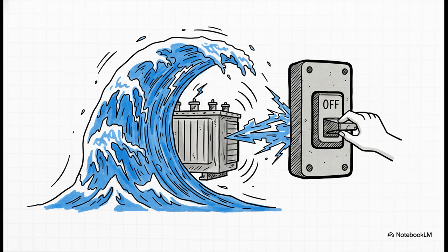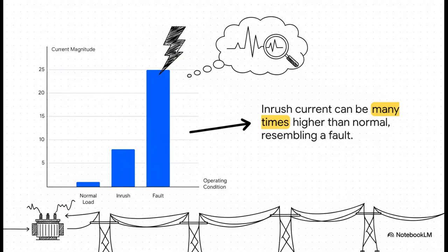When a transformer first gets connected to power, it draws this huge but totally temporary spike of current to get its magnetic core all fired up. It's a normal, harmless part of its startup sequence, but to a simple relay, that huge spike can look exactly like a catastrophic failure. And this chart really shows you the problem. Your normal operating current is way down here. Then look at the inrush current. It can be several times higher. To a relay that's just looking at the size of the current, that spike is a 5-alarm fire. So the big question is, how does the system possibly tell the difference?